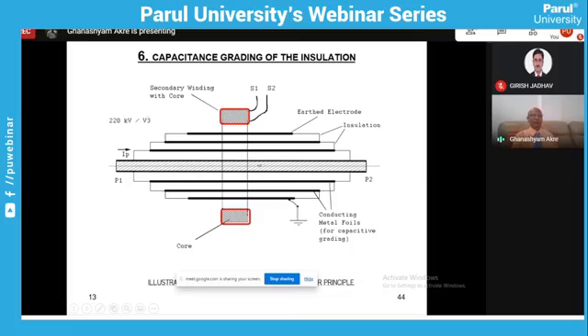You see, this is the section of the primary winding. This primary is at high voltage, and this is the section of the core which is connected to earth potential. Now, how is this insulated? It can be insulated by single paper layers, say 25-30 millimeter for 66 kV, and that can also insulate it. Or it can be insulated by inserting metal foils in between, so that each metal foil with respect to the primary will have its capacitance, and this will act as a capacitor divider. So the voltage across each capacitor is kept such that it is equally divided.